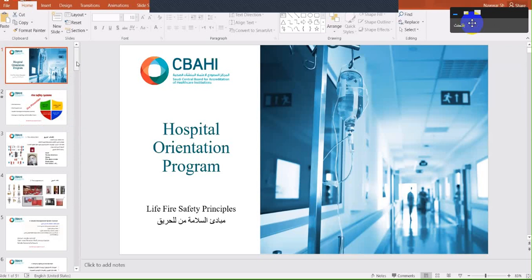That's the first element. The second element: have the key functions to discover fires by having an effective fire alarm system, distributed and well-maintained by authorized people. Third element: be able to suppress fire, either by portable first aid tools like fire extinguishers and fire blankets in the areas, or by fire hoses, sprinkler systems distributed, and the right clean agent system in areas that require it.